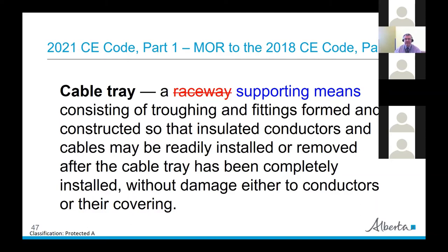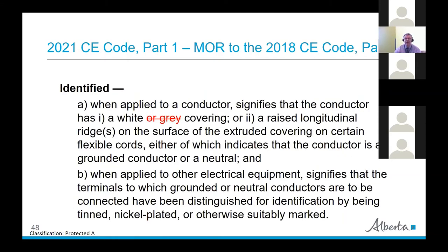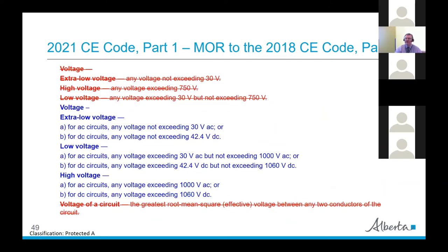Another highlight: the identified conductor. Most SCOs know the identified conductor — the neutral — is white or gray. Gray was used because it was easier to manufacture, but over time that's changed. Now with communications cables often using gray for something else, they've started the process of getting rid of gray as the identified conductor, so it will just be white going forward.